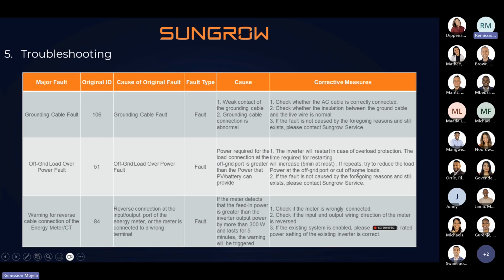Then we have the troubleshooting steps. With the troubleshooting part, I don't like to go through it because the app is also a troubleshooting manual for you. Whatever fault you get on the system, the app itself will tell you that you have this fault, how to solve it, and what the cause of that particular fault is. What you see here on the app is that you have a grounding fault, which is error 106, and it will tell you the cause of origin is the grounding cable fault, and the cause of that fault is weak contact of the grounding cable or the grounding cable connection is abnormal. Then it will tell you what to do to solve that particular fault. And if all those steps don't work, then you can contact Sungrow.